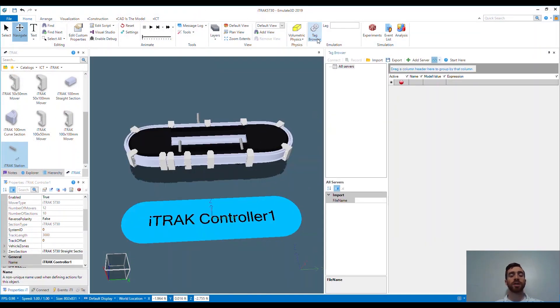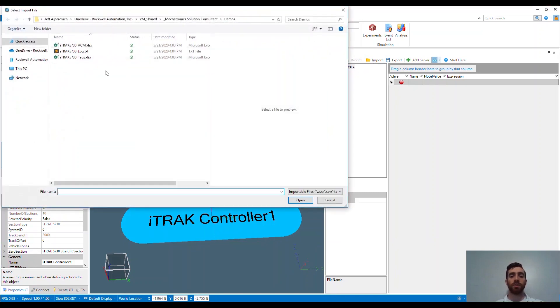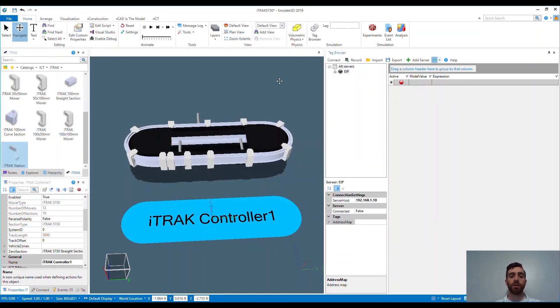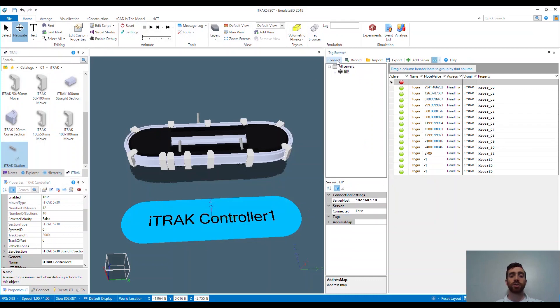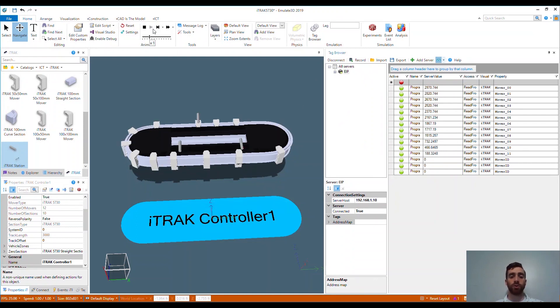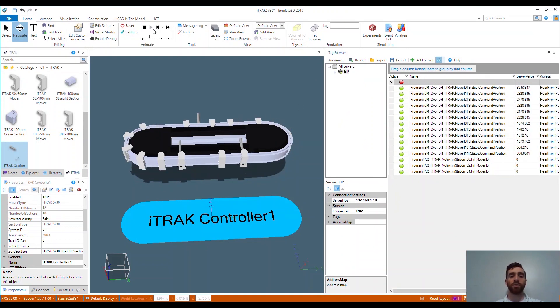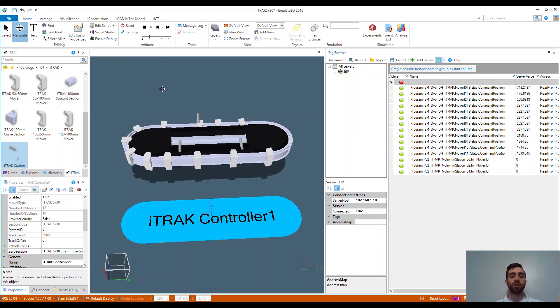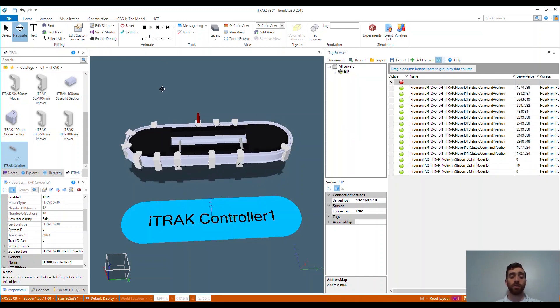Step one is to connect the controller. In the tag browser, we can import the tags that we previously generated. From here, we just click connect and you'll start to see the controller tag values change. For this to work, I already had my computer ethernet on the correct network and hooked into the controller. From here, I play the model and you'll see the system function exactly as it would in real life using the same code.